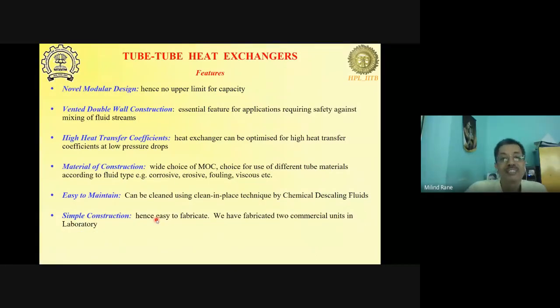These are some of the features of the tube heat exchanger. There is no upper or lower limit in capacity. As I said, we have done even a couple of kilowatts duty, all the way up to a 270-ton ammonia refrigeration system. We have done these superheaters for that. And if somebody asks us to do it for 3,000, we'll not blink an eye. So there is no limit on the capacity. It is vented double wall, so it is very, very safe. No chance of mixing of the fluids.